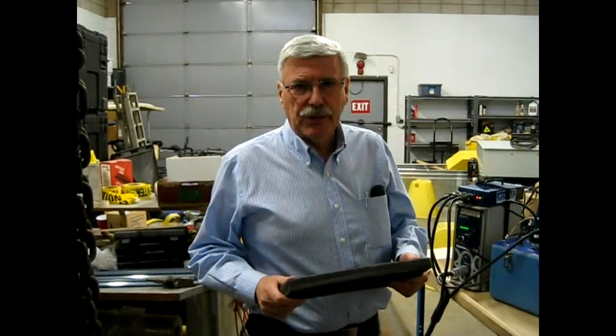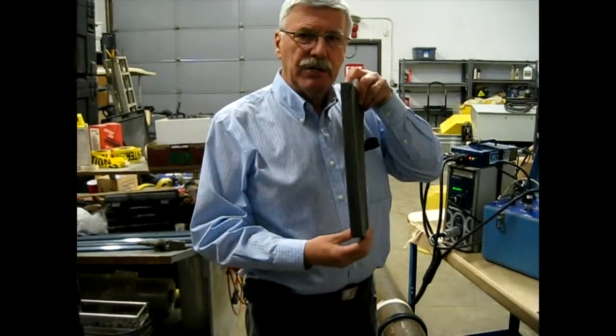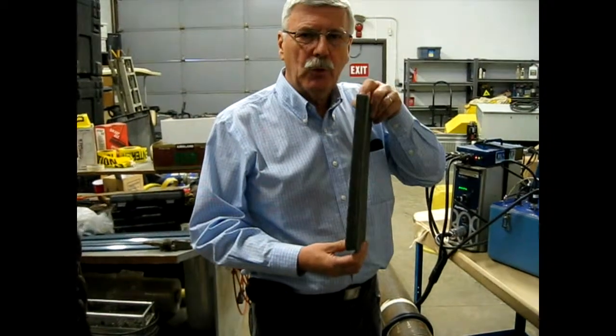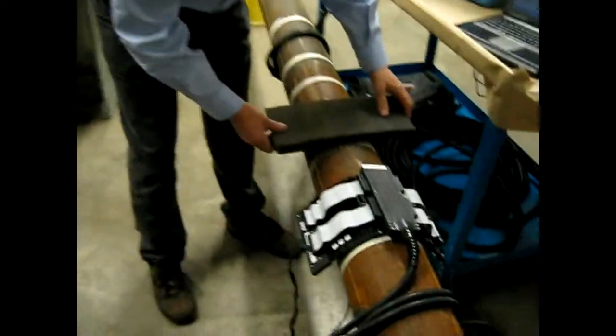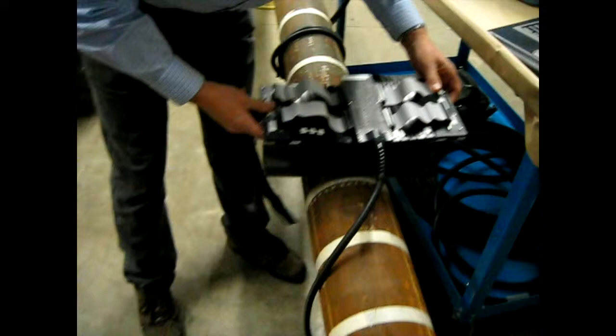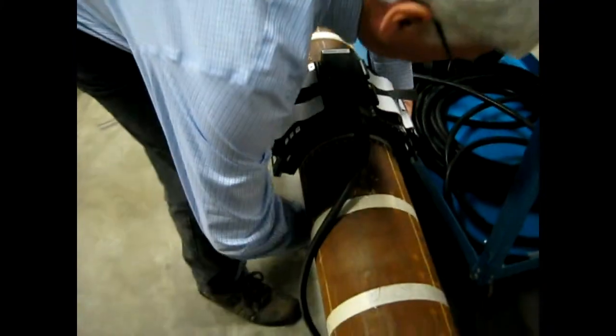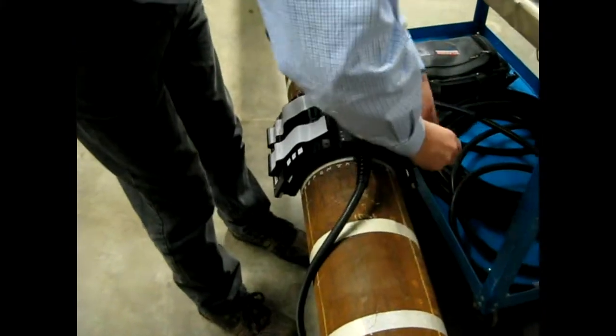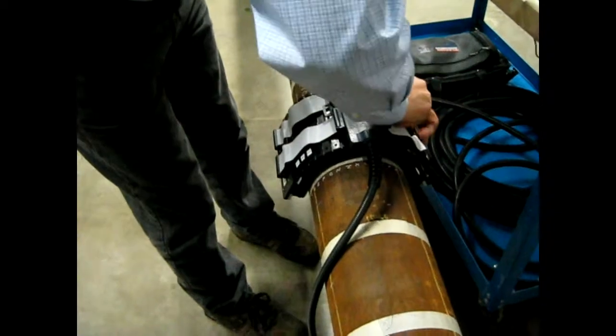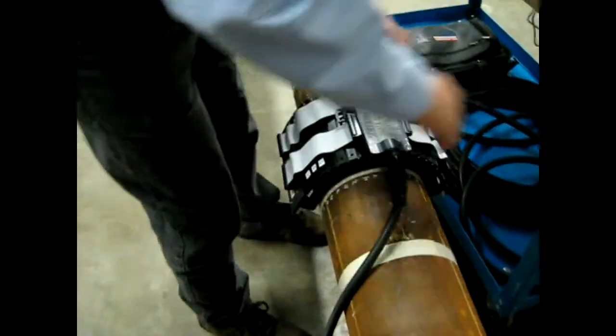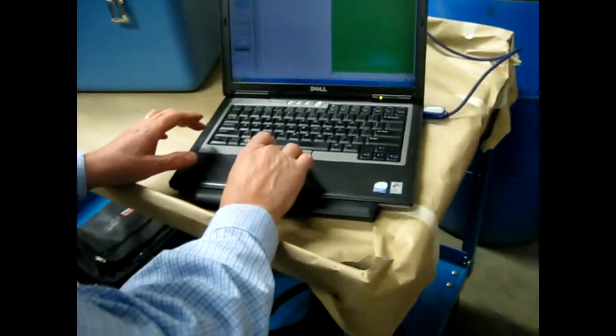The next part of the demo will show you how it works through insulation. In this case I'm going to use a 1-inch thick piece of foam between the blanket probe and the pipe. This is over top of the part that has the internal corrosion. So we've placed the blanket probe, and now we're just going to start the file.